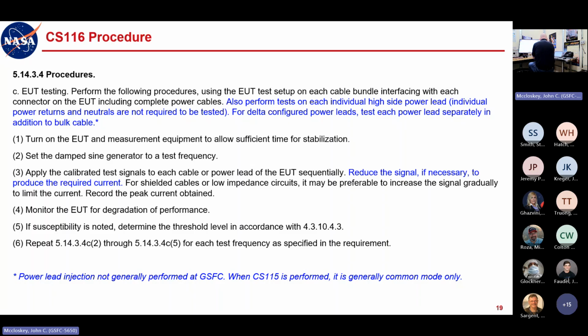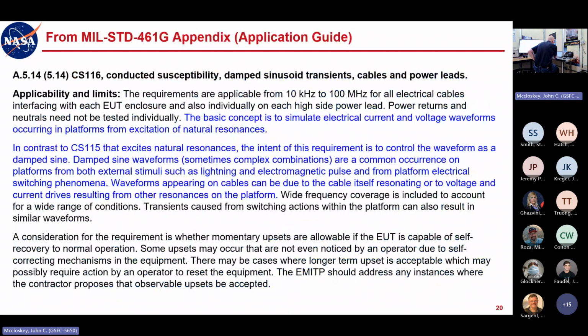What that helps with, and I've done this when we've actually run this test, is if you're doing this test on multiple cables, you basically can run the pre-calibration once, to just know that you're getting the desired signal for a given signal level. But then once you're testing the individual cables, the response is probably going to be different on each cable. I just adjust the signal level accordingly to get the desired current on each cable. Right. So especially if they're in a similar bundle, the impedances should be fairly similar. So anyway, getting pretty close to the end of this portion, and then we can start hooking up hardware.